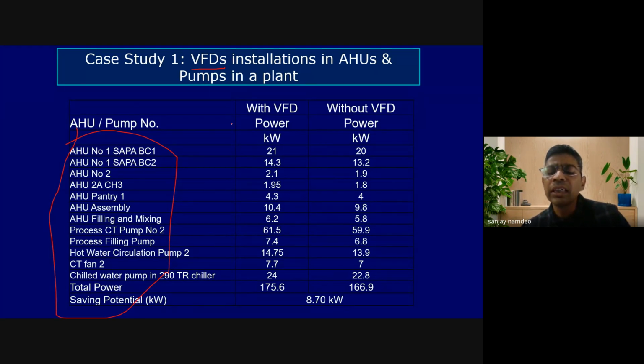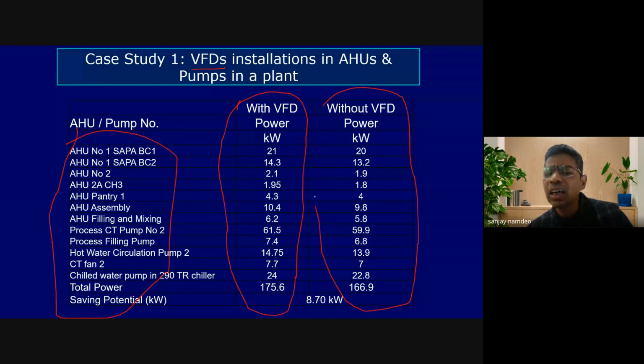During the audit, when we actually measured the performance, we were told that they had recently gone for the VFD based on the technology provider's suggestion, and the technology provider had given them a guarantee of around 20% savings. So we measured the power with the VFD in line, and we also measured the power by bypassing the VFD, or let us say after the VFD and before the VFD. What we saw was a difference in the power consumption: with the VFD, the power consumption has slightly increased rather than coming down.